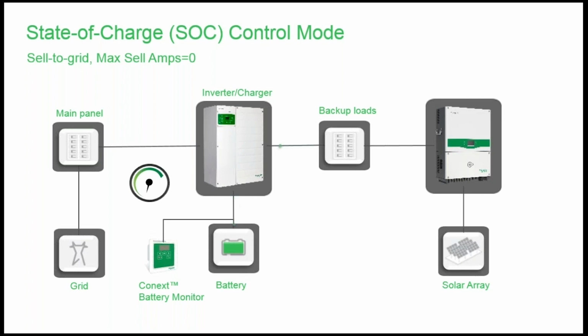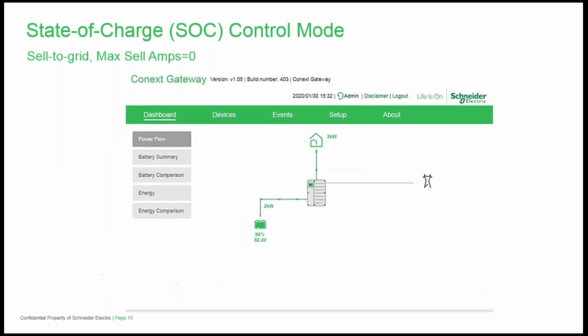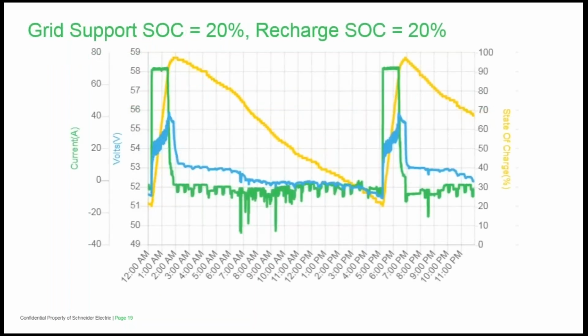You can see the power coming out of the battery and discharging to support your backup loads, drawing virtually nothing from the grid. Here's the actual power flowing with a 1400 watt microwave and other household loads. Note 0 power is being drawn from the grid. Note how the XW Pro prioritizes battery power down to grid support state of charge, and the recharge state of charge triggers a charge. So I can discharge my batteries and support the load completely on battery. And then when I get down to recharge state of charge, it'll start a new charge cycle.